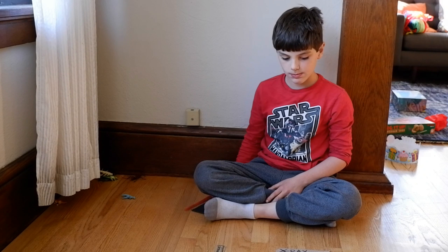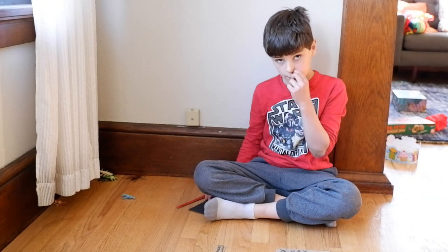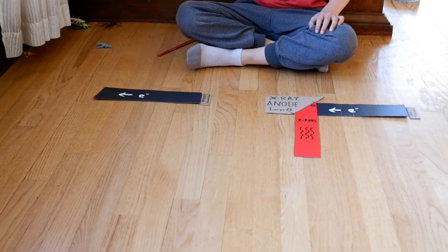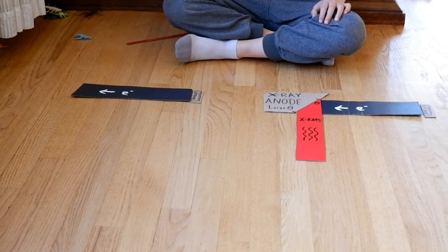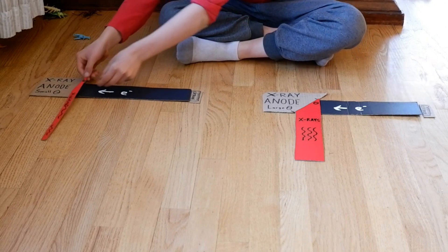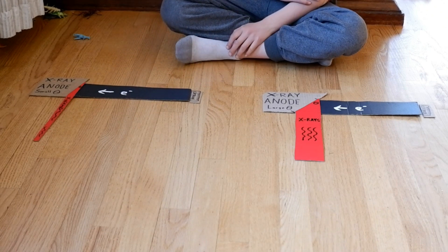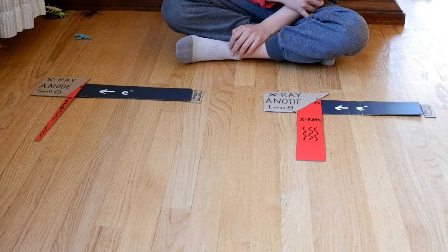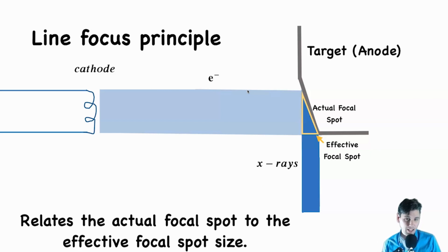Now we're going to compare that relatively large target angle to a small target angle case. You can see here's the electron beam coming out of the cathode — the actual focal spot size is staying the same size. Then our electron beam is now ramming into an x-ray tube with a small target angle, and you can see the width of our x-ray beam is much smaller. The amount of energy we deposit on the anode is actually the same because the width of our electron beam is the same, but because we have a smaller target angle, the effective spot size that the patient will see is significantly smaller.